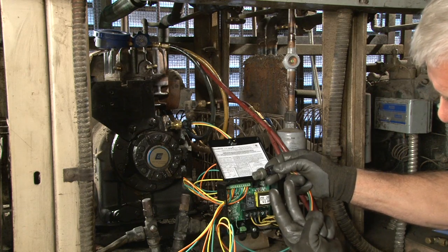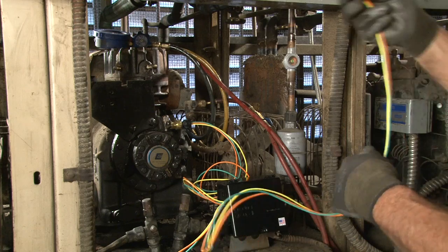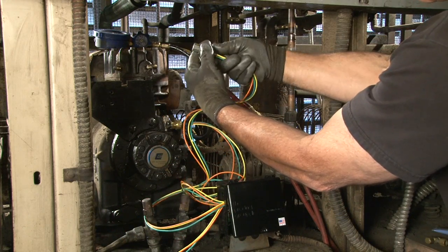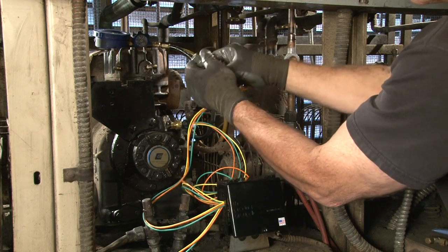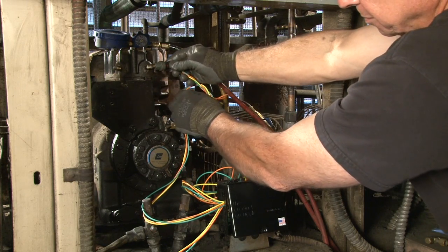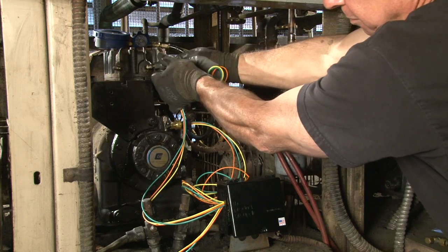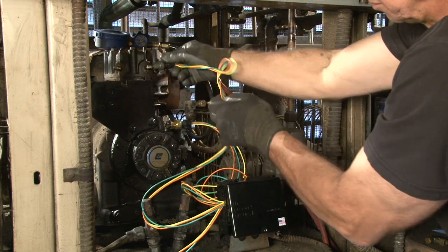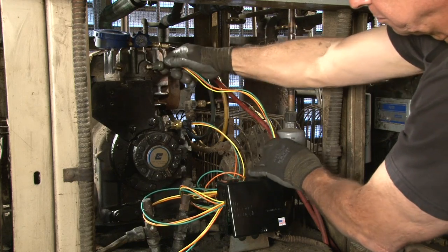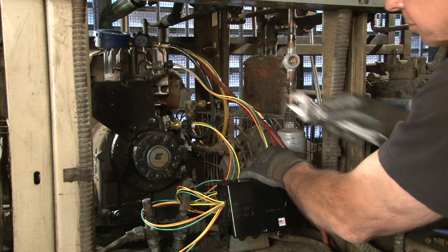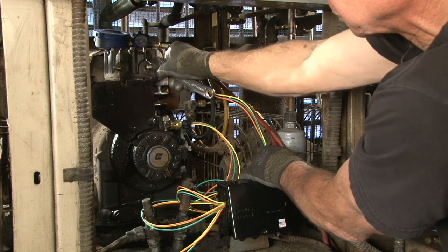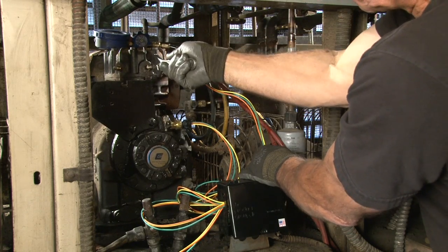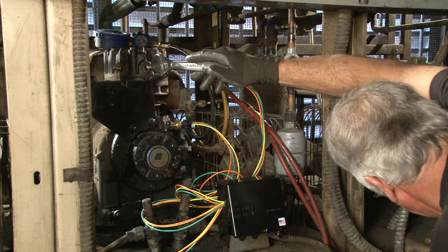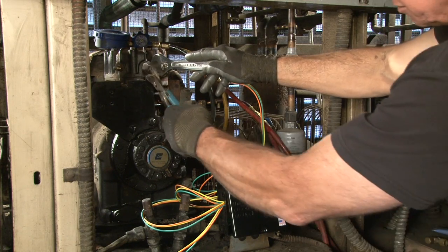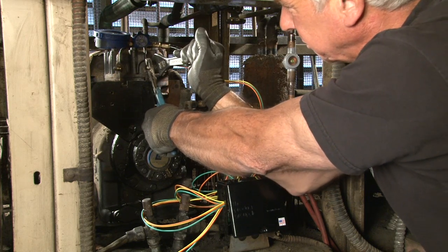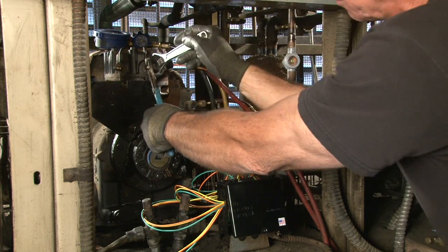Now the technician is going to install the channel 2 high pressure transducer onto the male flare adapter on the discharge head of the compressor. Once again, he's backspinning the transducer approximately 7 times in order to allow the wiring to spin with the transducer onto the adapter. Notice the wire straightens out. He hand snugs the transducer, again uses the small adjustable crescent wrench, and by using the backup channel locks ensures that the fitting is not broken while tightening the transducer.